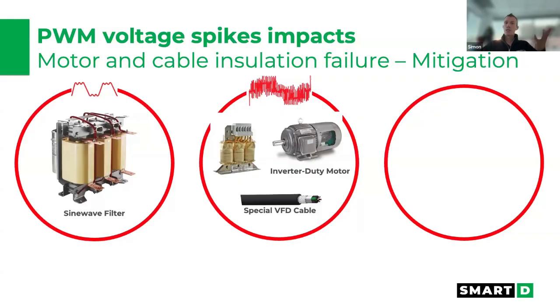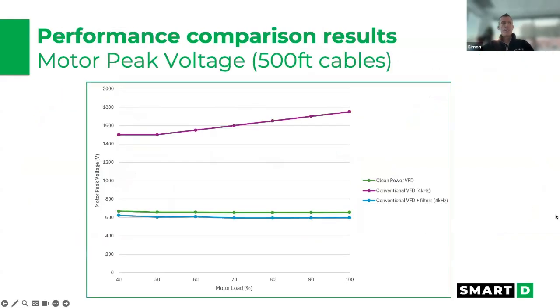And so if we go back to the lab, we can clearly see this is with a 480 volt unit, 500 feet of cable. If you don't do anything with 500 feet of cable, you're going to get near 1800 volt peaks, voltage peaks definitely higher than what your motor and your cable is rated for. On the contrary, you can see how you're really delivering a very constant voltage through the clean power VFD, which is essentially equivalent to the sine wave filter.